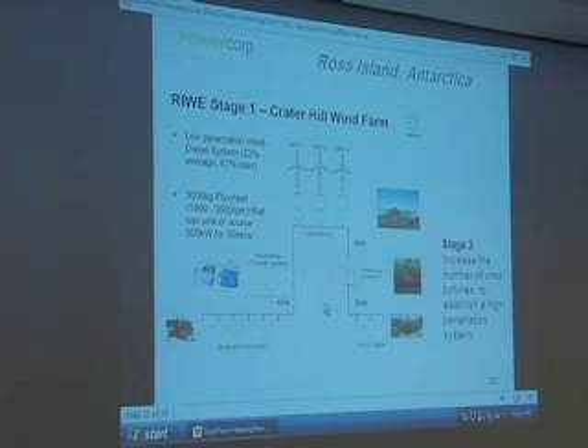So there had to be a magic box installed to convert the frequency between the 2 systems. They've got 6 in that picture, but I think it's now up to 8 diesel generators on the American side, in the order of 1,400 kilowatt machines, big Caterpillar engines. On the New Zealand side, there's 3 200 kilowatt little machines.